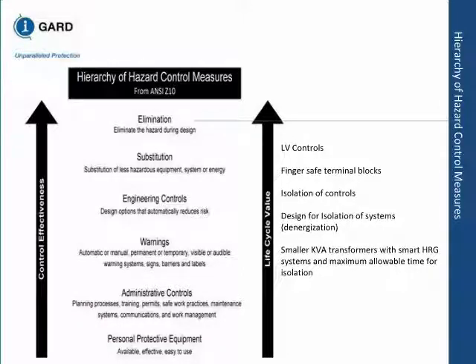And one thing you can do is design for isolation of the system. A good design starts from the bottom up. You don't design a system and let maintenance people maintain it and operating people operate it. You see how they're going to operate and maintain, and that's how you design the system. Can the system be safely energized and de-energized? If you have, for example, double-ended two lineups, do you have two panels for control voltage so you can isolate?